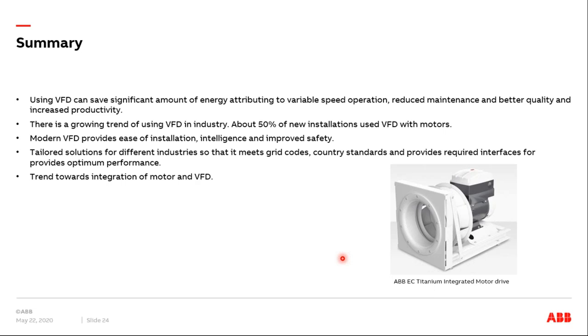The last thing I want to say is that we had the motor and the drive as separate units, and the trend now is towards the integration of the motor and the VFD together. You see in the picture one of our products, what we call the EC Titanium Integrated Motor Drives. You have the motor and the drive together, which gives even more ease of installation, because the drive knows exactly which motor is used. It's really easy to hook up to the main power supply, because you just have three wires connected, and then you're done. It also saves a lot of space. So this is what I wanted to present. Thank you for listening, and let's all try to be more energy efficient. If you have any other questions, please go ahead.